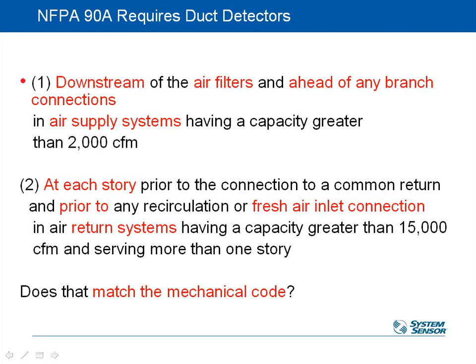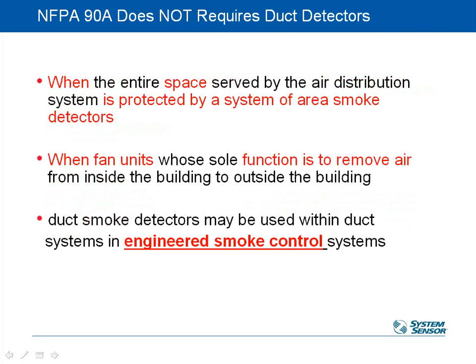All right, if you have a multiple story building with that 15,000 CFM that we talked about, basically you have to put the detector on that floor, on the return for that floor only, before that return mixes in with the common return from other floors. So basically we want it to detect that air only, not the mixture of that zone and other zones. So hopefully that makes sense there as well. A few more code-related things, and then we'll talk about product.